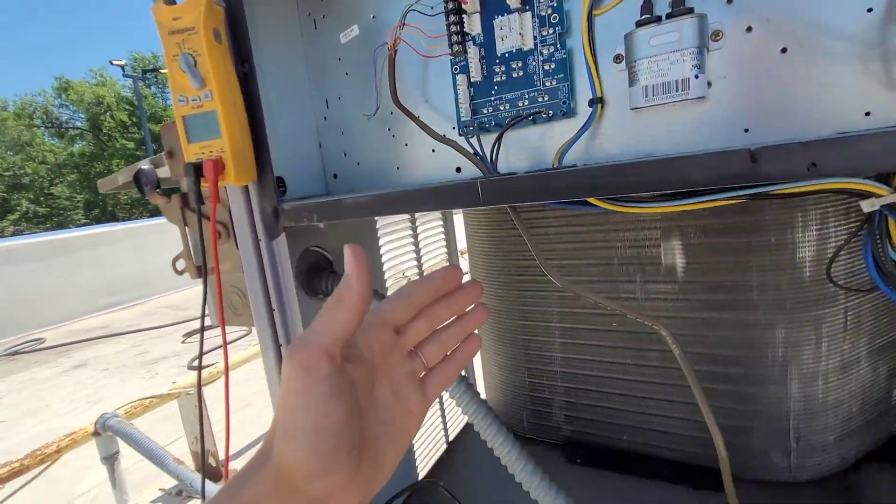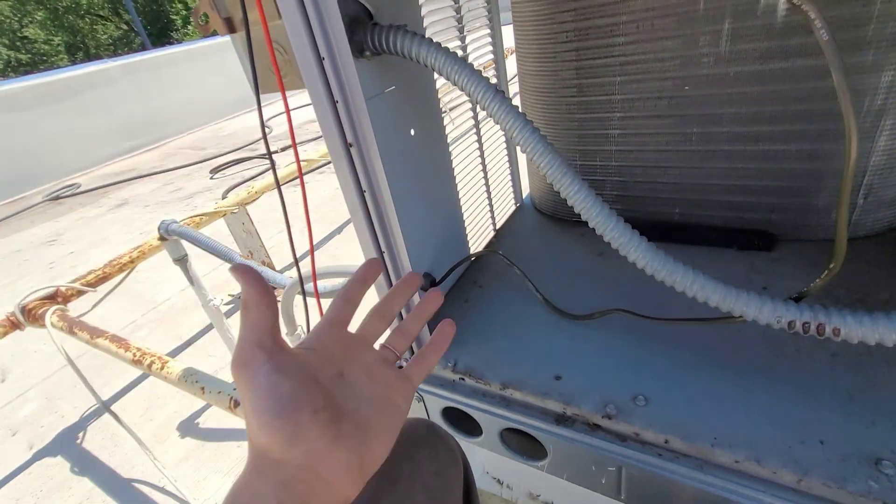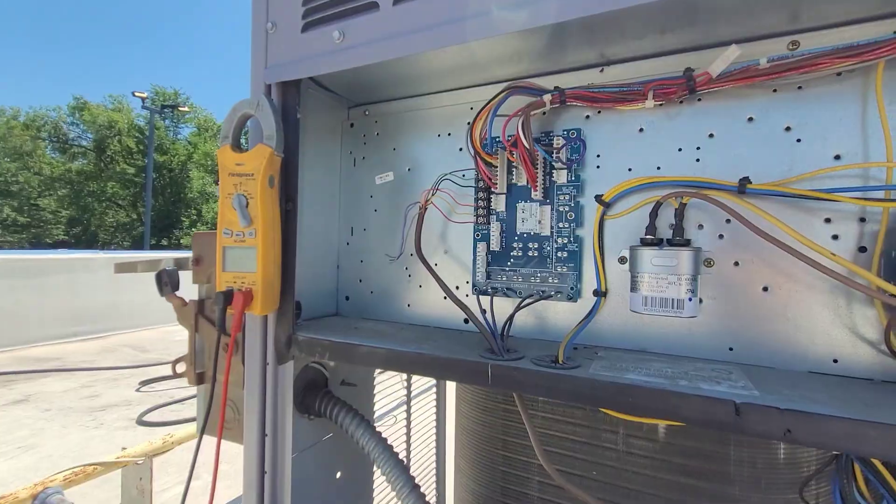It was clearly just a low voltage problem on the unit itself. But that can really save you a lot of time if you're not sure where the short is in the system. Separating the thermostat wiring from the system really helps, because it cuts your troubleshooting in half. I didn't have to do anything to the thermostat or to the wire going into the building, because I knew right away after separating it and checking my ohm readings that the problem was in the unit and not with the thermostat wiring.